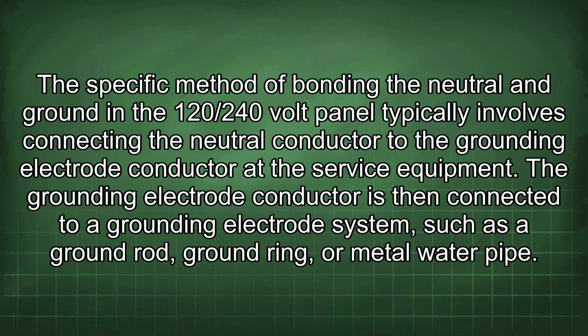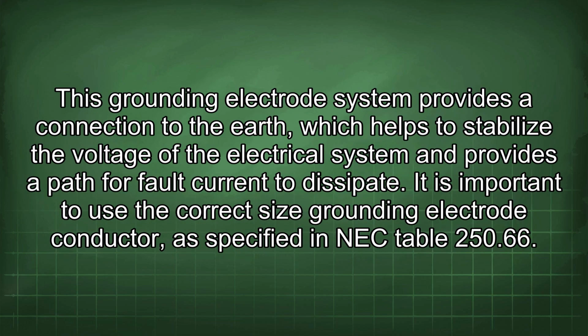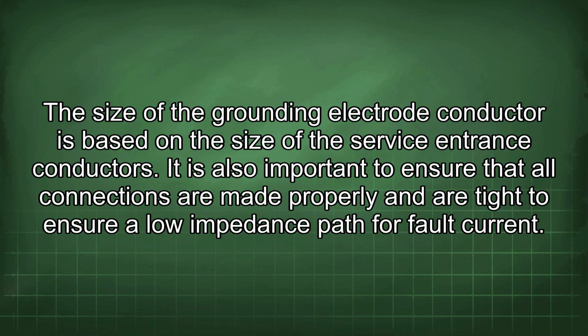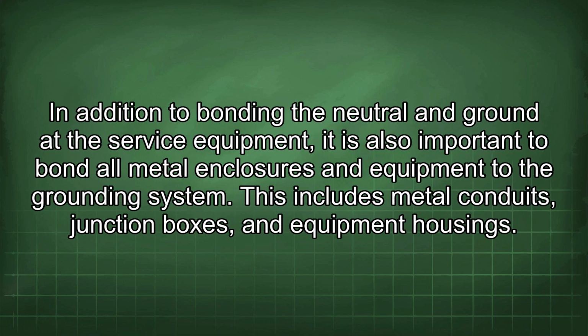The grounding electrode conductor is then connected to a grounding electrode system, such as a ground rod, ground ring, or metal water pipe. This grounding electrode system provides a connection to the earth, which helps to stabilize the voltage of the electrical system and provides a path for fault current to dissipate. It is important to use the correct size grounding electrode conductor, as specified in NEC Table 250.66. The size of the grounding electrode conductor is based on the size of the service entrance conductors. It is also important to ensure that all connections are made properly and are tight to ensure a low impedance path for fault current.